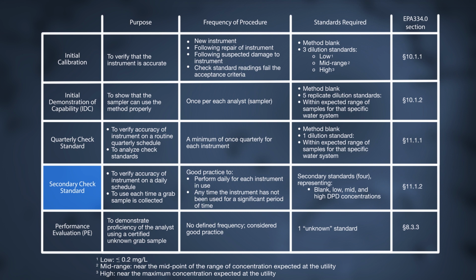Secondary check standard verification is used to verify the accuracy of the instrument daily or each time a grab sample is collected. It can also be a surrogate to verify instrument performance between primary standard verifications. Secondary standards may be purchased for use with most DPD spectrophotometers or colorimeters. The accuracy of secondary standards must be verified on each recently calibrated spectrophotometer or colorimeter for which they will be used. Secondary standards may not be used to calibrate the instrument.